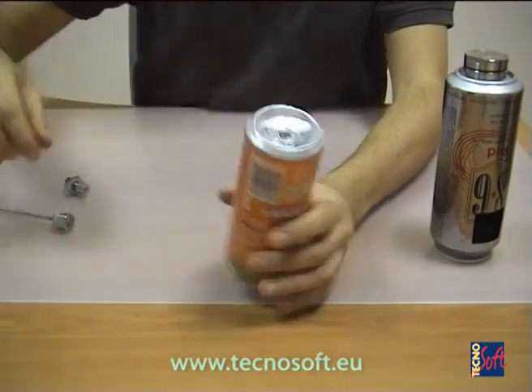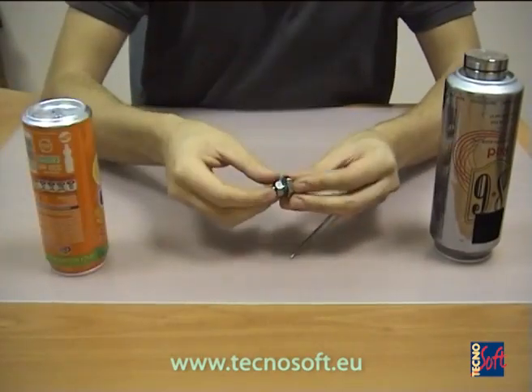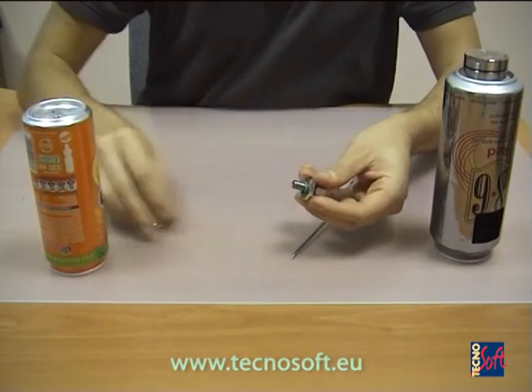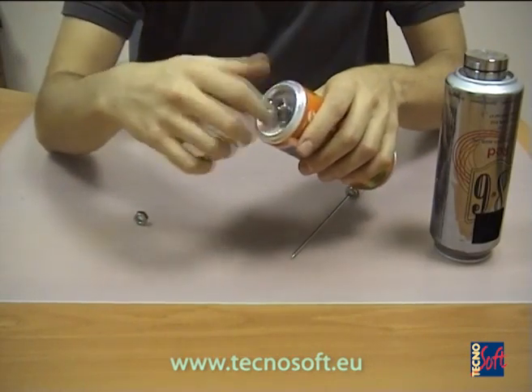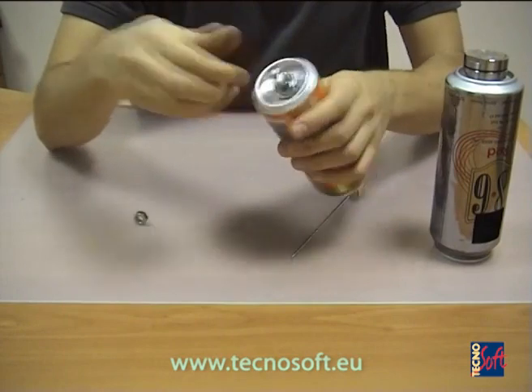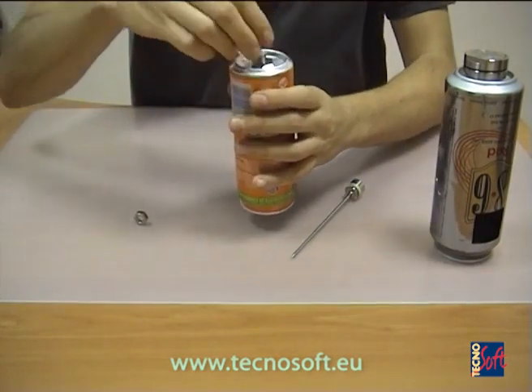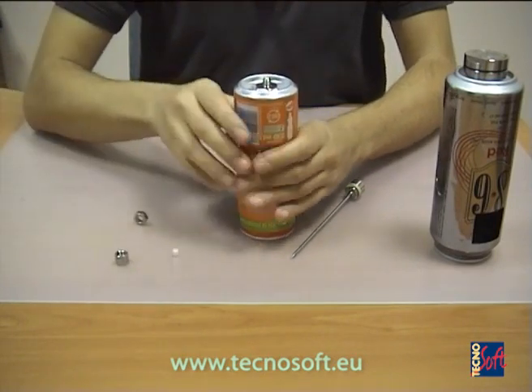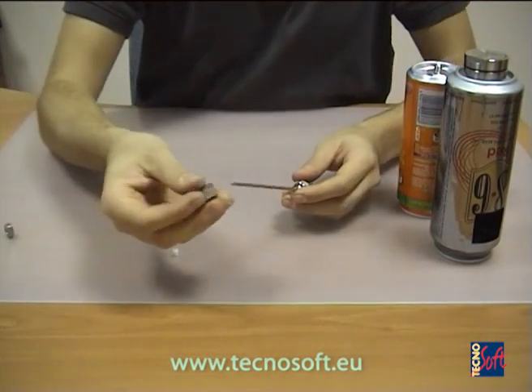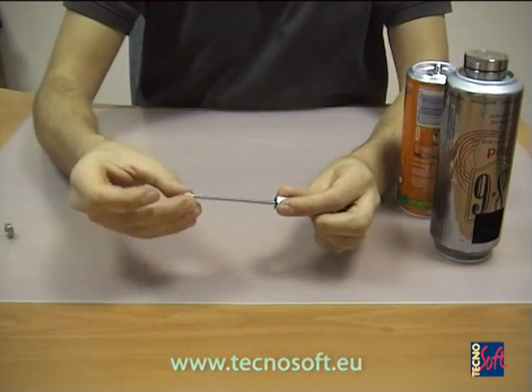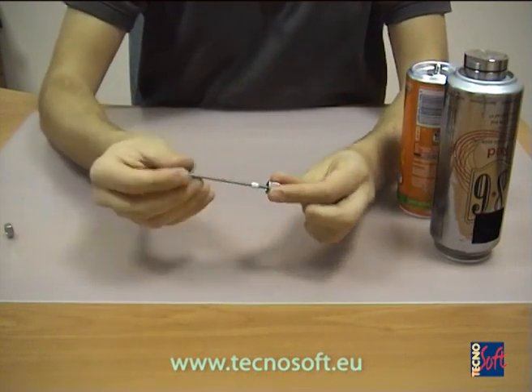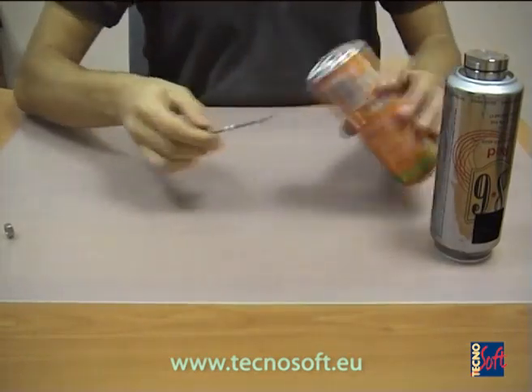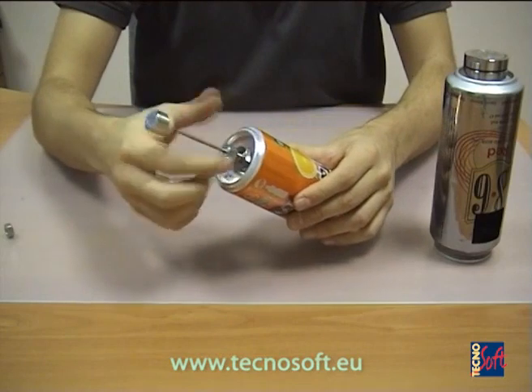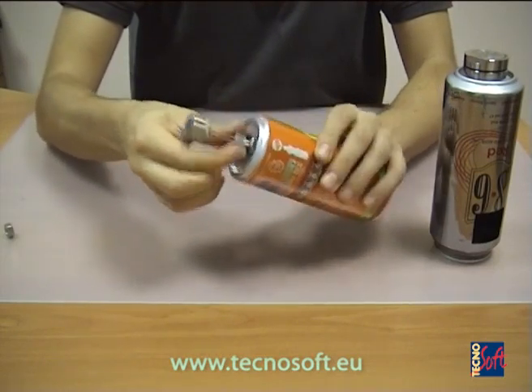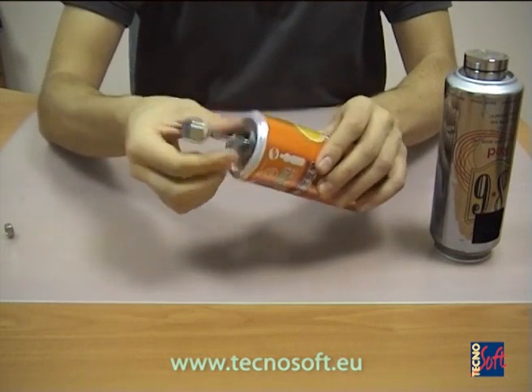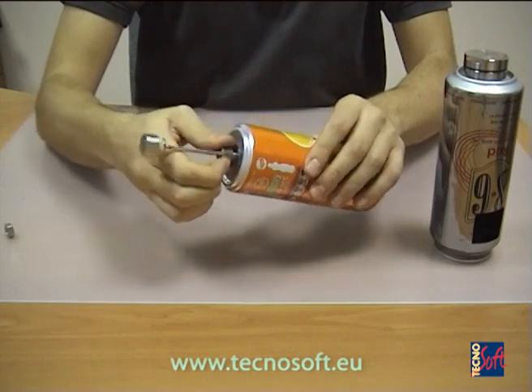And here one with a big rivet for the locking nut. We remove the counterbolt that we are not going to use now. We screw the locking nut in the rivet. We remove the top holed bolt with the Teflon olive, and as already described, we put the holed bolt on the probe, in this case of this S-micro, then the Teflon olive to stop the run of the probe inside the locking nut, and in this way we can adjust the depth of the probe inside the can just by screwing and unscrewing the top holed bolt.